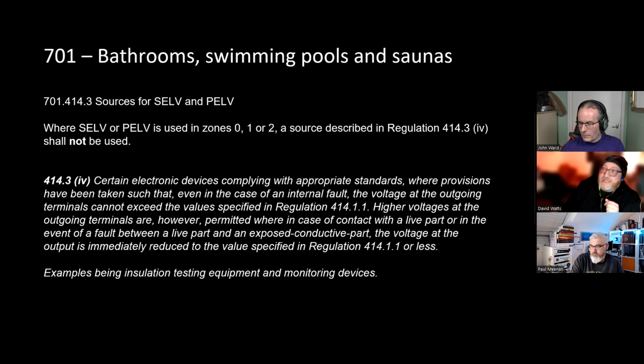And I expect what they're going to say is that in cases where you have wet things, that's not a good idea. So without doing any more real investigation as to what kind of exact items this is, an example in that regulation is insulation testing equipment and monitoring devices. Combine a device that achieves protection that way, where it can have a potentially higher voltage on the outputs, with a wet environment, and I think the regulations say that's not a good idea. So you'll see that in 701. Did you include all the slides for that in the others as well? All right, we'll see you again in a minute.